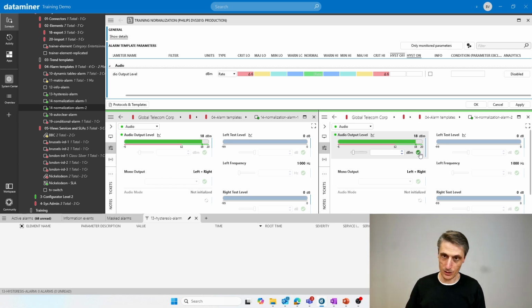And I can go back to the left hand side as well, as long as I do that more slowly and not too fast. There's no big rate change detected here, so my alarm thresholds are immediately progressing along with me, and I allow these kind of subtle changes. But as soon as one of those parameters is doing a quick change and I suddenly have a quick increase, then I want to generate an alarm. Let's say it's 9 and it now in one go goes to 15 or 18 into the critical zone, then it will generate a critical alarm, a short critical alarm.